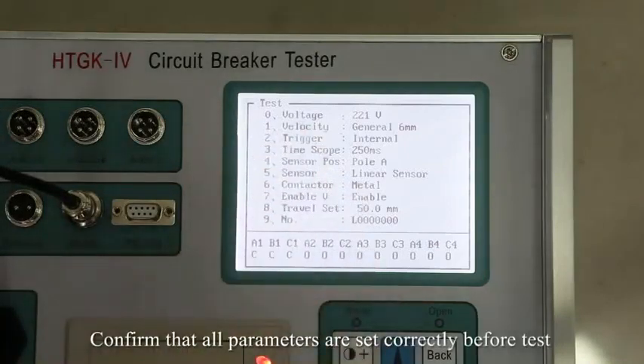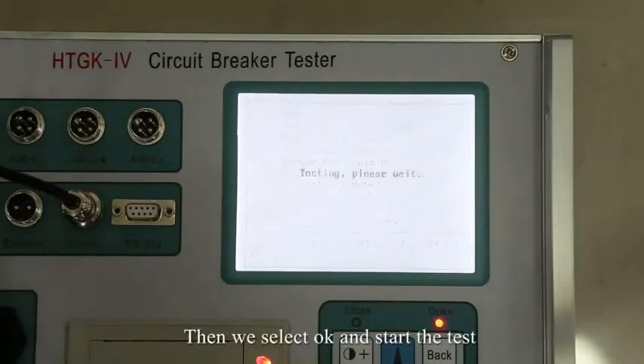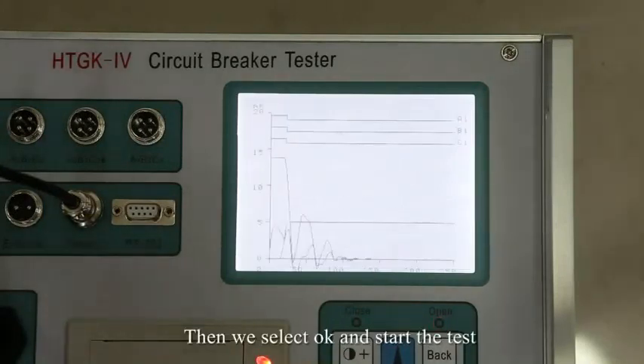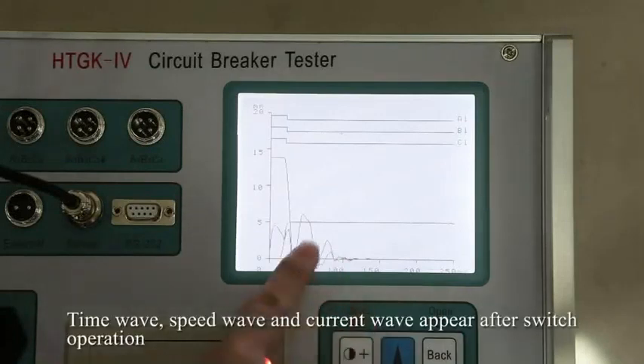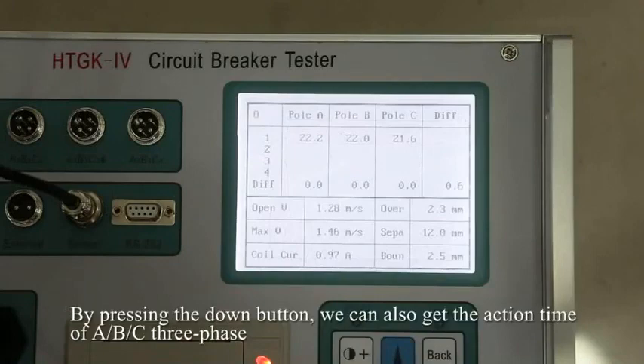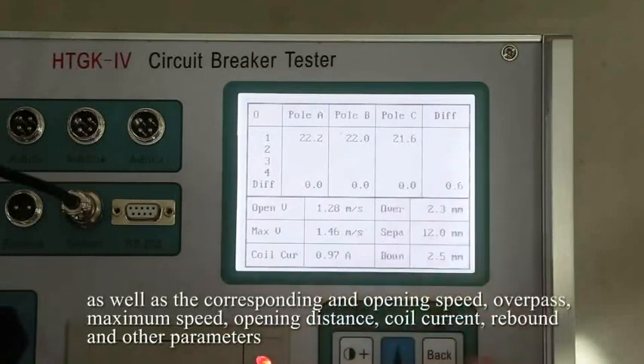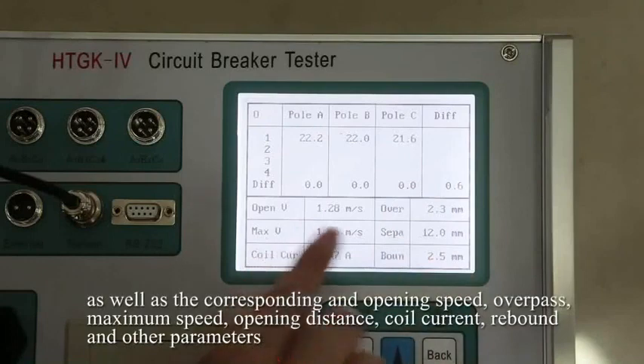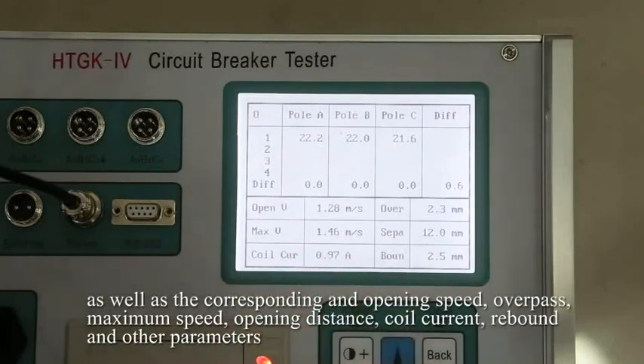Confirm that all parameters are set correctly before the test. Then we select OK and start the test. Time wave, speed wave, and current wave appear after switching operation. By pressing the down button, we can also get the action time of A, B, C three-phase, as well as the corresponding opening speed, overtravel, maximum speed, opening distance, coil current, rebound, and other parameters.